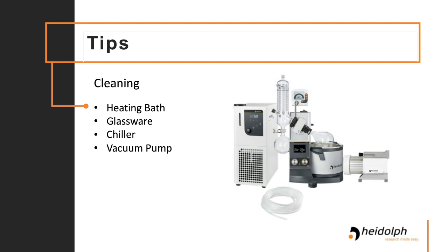Keeping your glassware clean is not only important for the longevity of it, but also to make sure you're not getting contamination. There's a couple of methods of cleaning it. The quick and dirty way is to run a solvent-only process. That'll flush out the glassware system, making sure there are no products or anything in there. Other methods include cleaning it by hand with a brush, or auto-cleaning it.